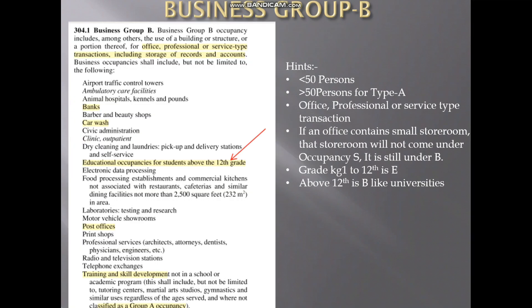Then, Business Group B. Business Group B is for groups with less than 50 people — if it is more than 50 people, then it will be occupancy type A. Mainly we use Business Group B for office, professional, or service type transactions, including storage of records. Because sometimes in an office building there will be a small place for storing records, and we cannot call that small store a storage occupancy — it is part of the office building and comes under Business Group B.